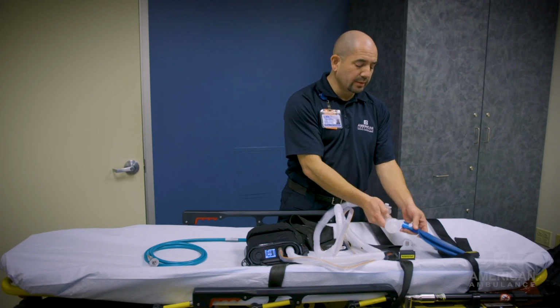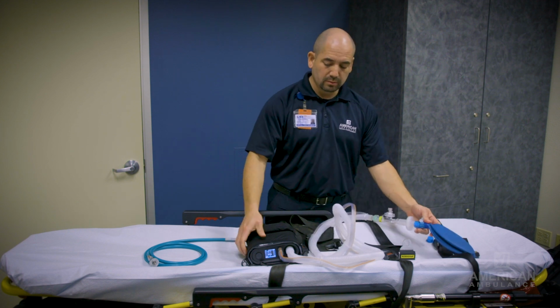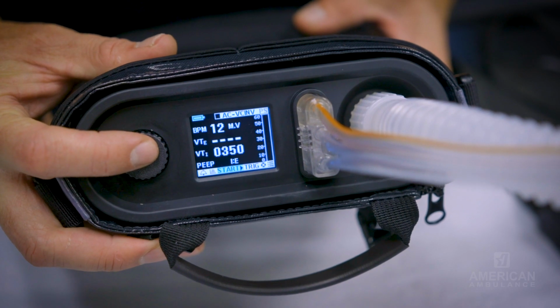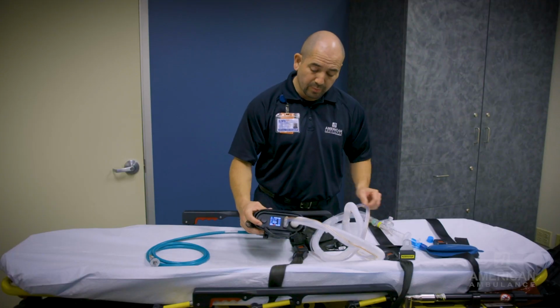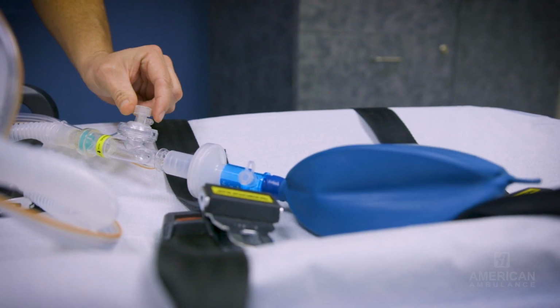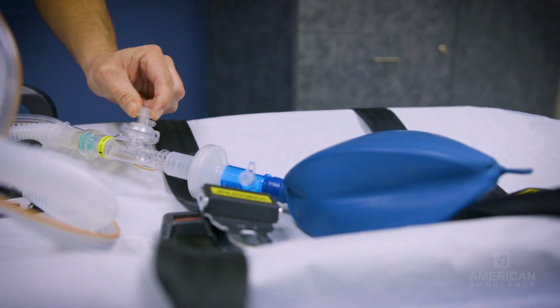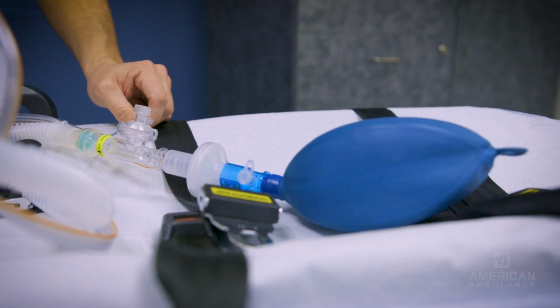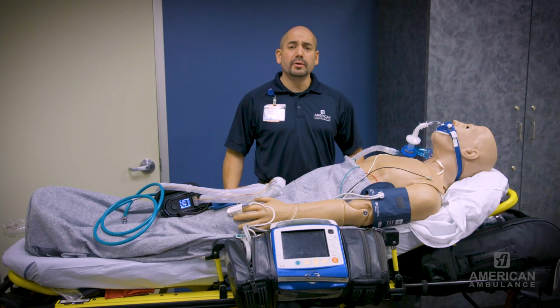After adjusting the FiO2, connect the circuit to the test lung, start the ventilator, and adjust the PEEP using the PEEP valve on the circuit. Grab some extra hands if needed and move the patient over onto our gurney. The patient will still be on the hospital ventilator during this move. On our gurney, hook up the cardiac monitor, the blood pressure cuff, the end-tidal CO2, and the SpO2 sensor.